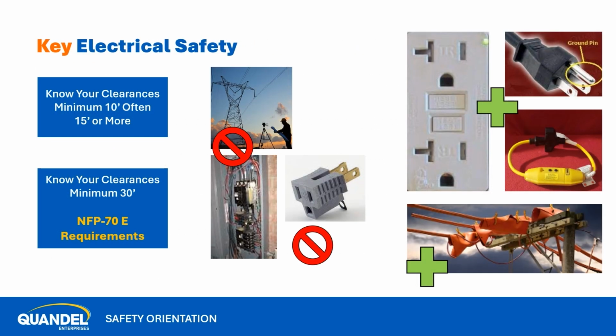To review, the clearance minimum is 10 feet, and when working between 10 and 30 feet from power lines, you must assume the NFPA 70E requirements discussed on the last 2 slides.